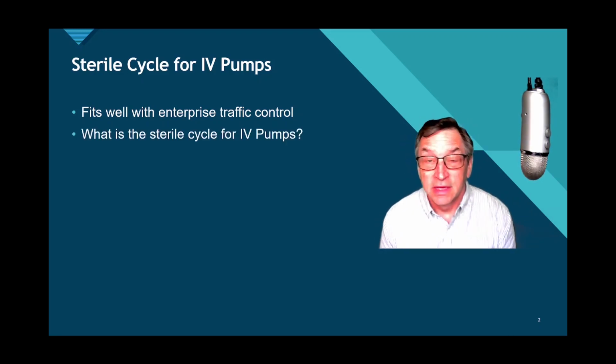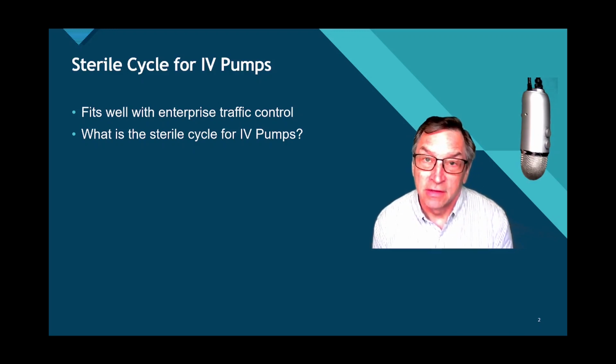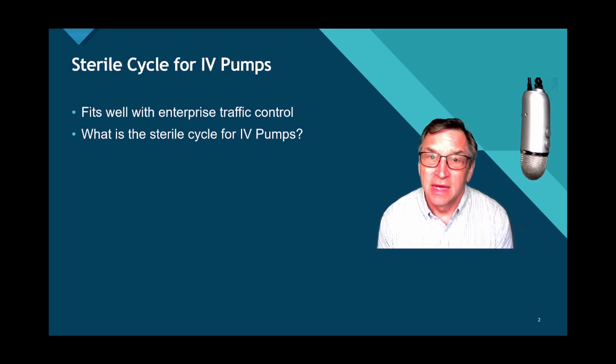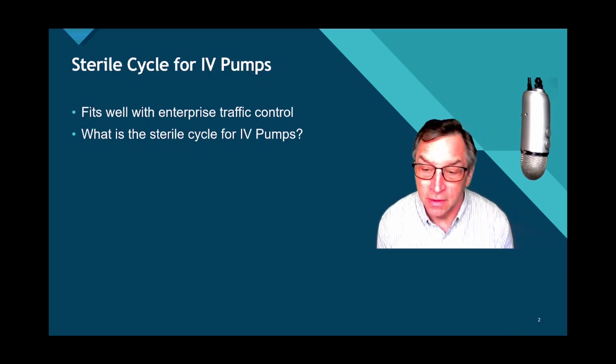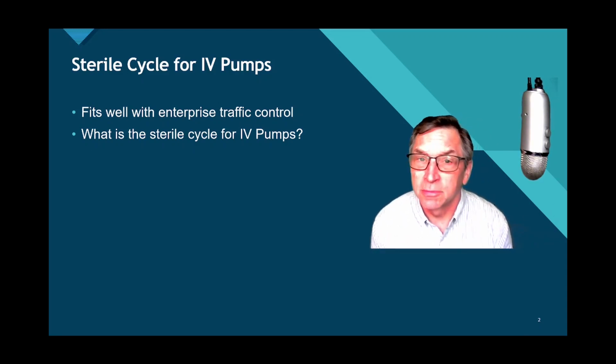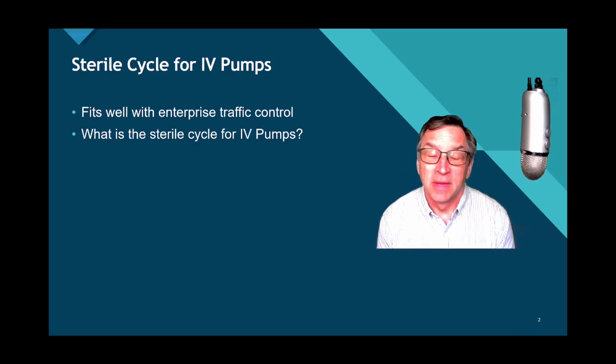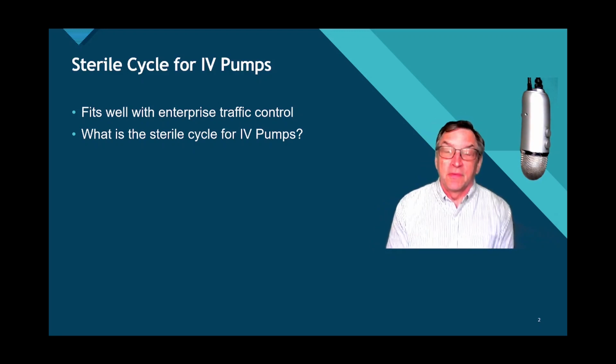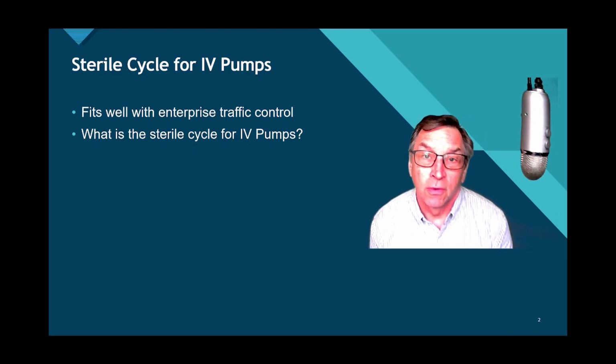According to regulations and manufacturer recommendations, the pumps need to be cleaned and inspected after each use on a patient. There are contaminants that can get on these devices from the skin flora, they call it, and the room itself. A centralized team is established that's a part of the infection control entity to address how you clean these devices. And they're responsible for retrieving and the cleaning, and sometimes they're also responsible for distributing back into the nursing units. This can be broken up a variety of different ways, but the cycle usually repeats the same.